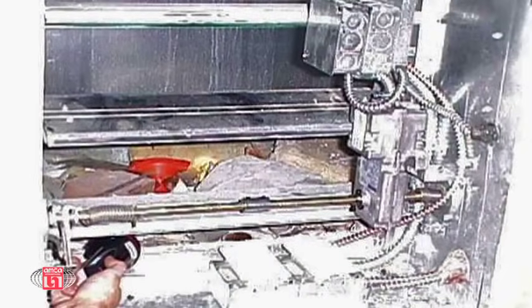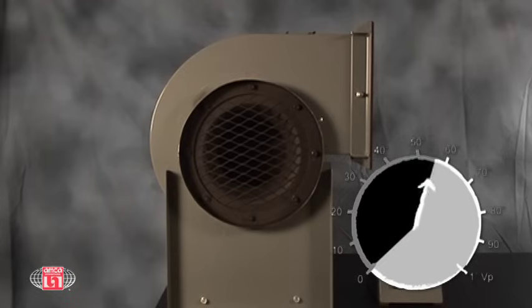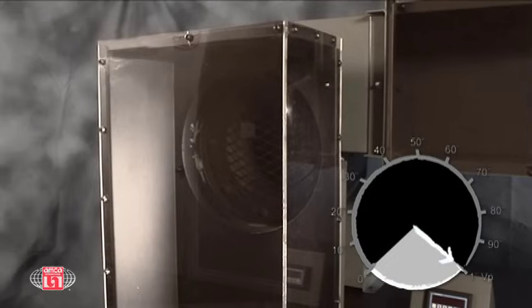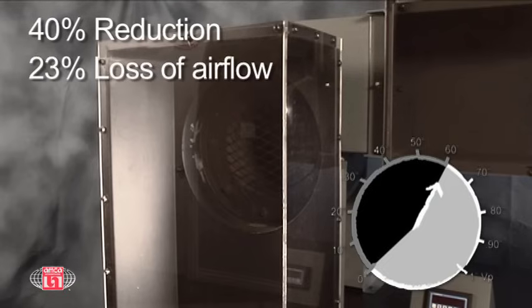Let's assume we use an open inlet as a benchmark, with the inlet velocity set to 1 inch of water velocity pressure. If we affix a poorly designed right angle inlet box directly to the inlet side of the fan, our velocity pressure is reduced to just 6 tenths of an inch water, a 40% reduction, which equates to a 23% loss of air flow.